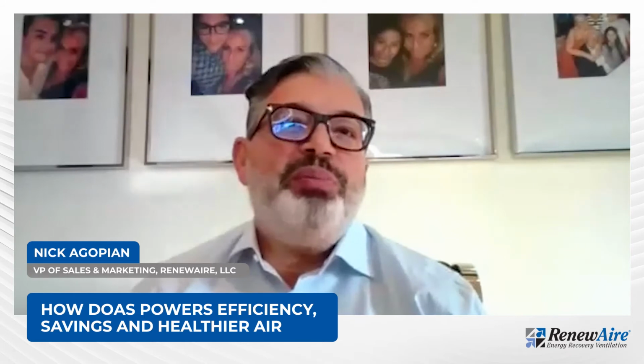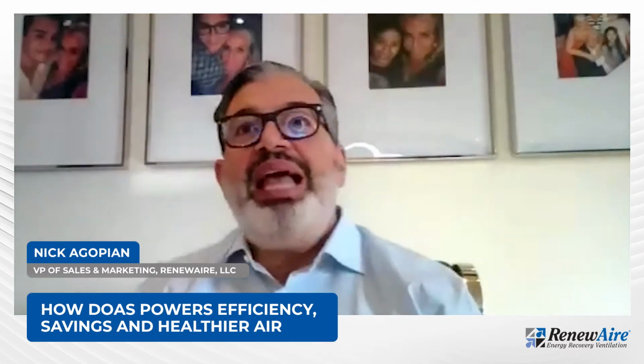So what's the first thing people do? They turn down the thermostat, and suddenly they end up with a condition of maybe 69 degrees and 75% relative humidity. And it becomes very humid indoors, where a DOAS can dehumidify and make it more comfortable for the individual, offering maybe a 40% relative humidity condition. And rather than being at 69, you could actually be up at 78 if you wanted to. And that would be better for your body.